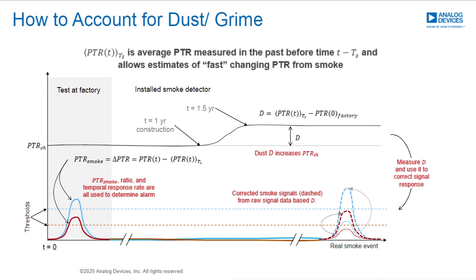If you think that the degradation to the actual smoke signal detection is going to be affected. So basically what this shows here is the way you would account for dust or grime over time. So at time 0, you take a measurement, you get some PTR off the chamber, and then as time goes on, you can continually just take measurements off the chamber, and as that response changes, it's due to some type of buildup on that chamber. And you can just simply account for that in your algorithm and set yourself with the new operating point when you're nulling out that background response.